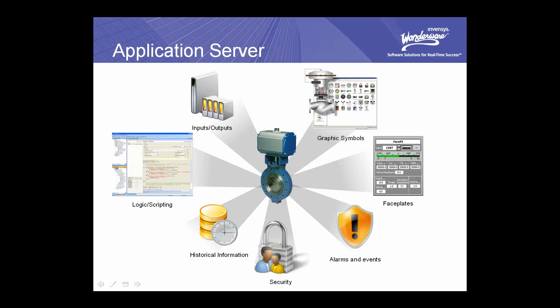We also have the ability to configure alarm limits for various data points associated with the device. In the latest release of Application Server, we introduced the ability to store graphics associated with the device inside the template definition as well. With that said, it is important to point out that Application Server is not the visualization system — it's not an HMI. Rather, Application Server enables you to separate the logical execution of your supervisory system from the visual system, while still containing those visual representations.